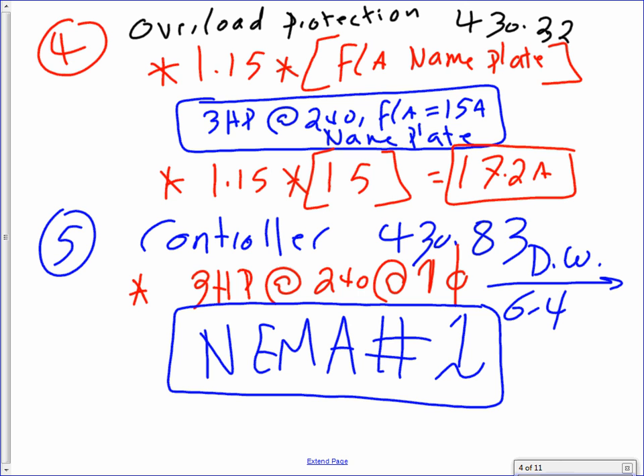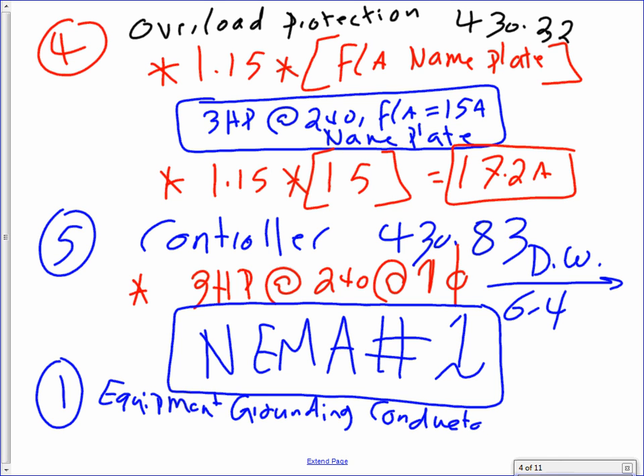The last thing I'm going to do, guys, is for the branch circuit, which is, what was it, number 1. I'm going to go back to number 1 here. And for number 1, I'm going to size the equipment grounding conductor. They call it equipment grounding conductor, EGC. Why? Because I'm going to use a flex that goes to this pump or PVC, and I need an equipment ground conductor. 2 hots, fine. That's just to send the power to the equipment. How about I need to ground the frame of the equipment?